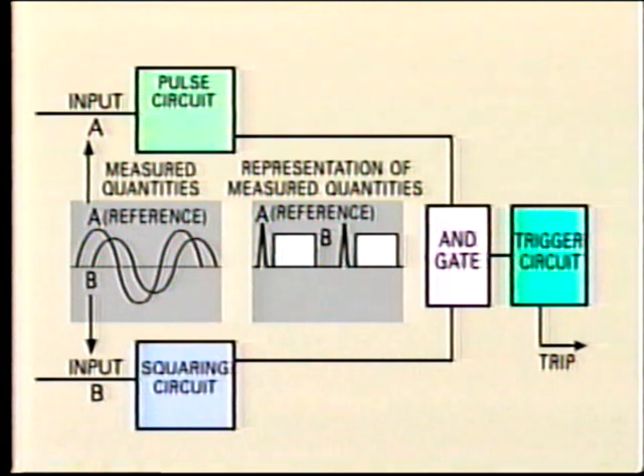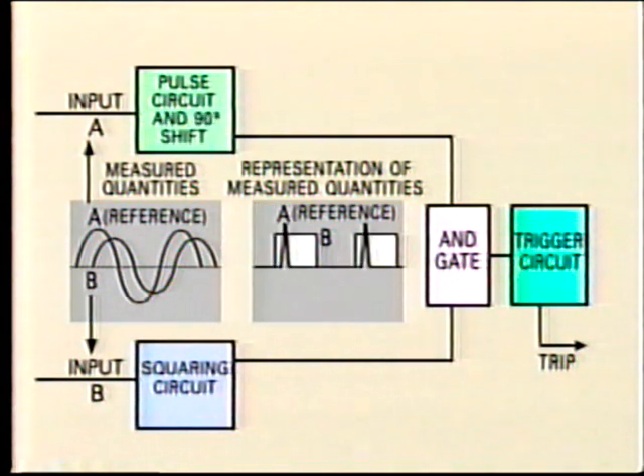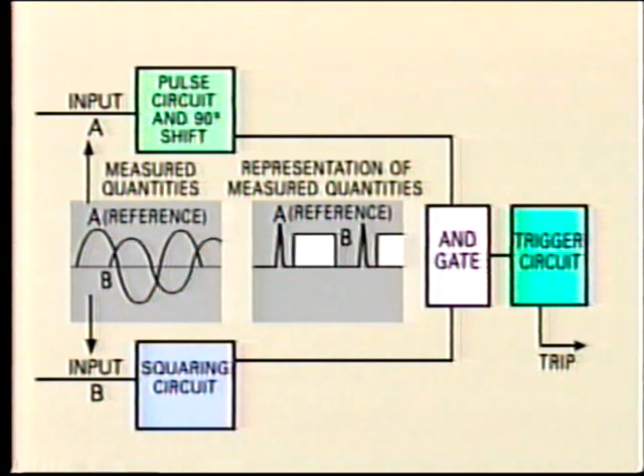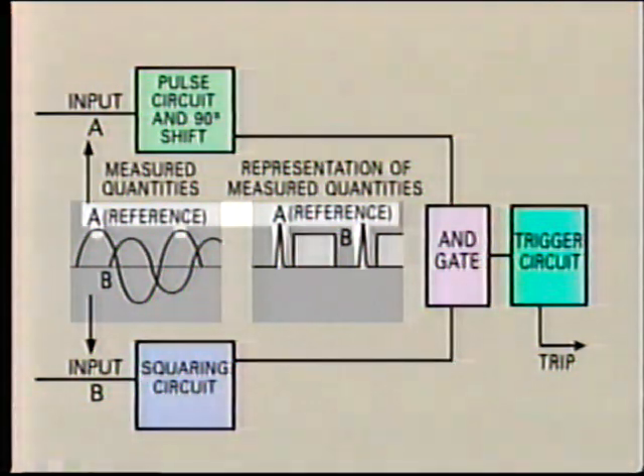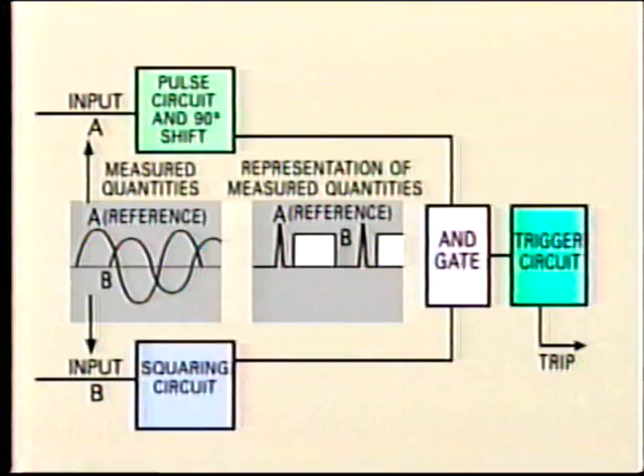A 90-degree shift is applied to the A quantity. Once the input phase difference becomes greater than 90 degrees, the pulse and block will not coincide and no tripping will occur. Note that the reference quantity A, in this case, remains fixed.